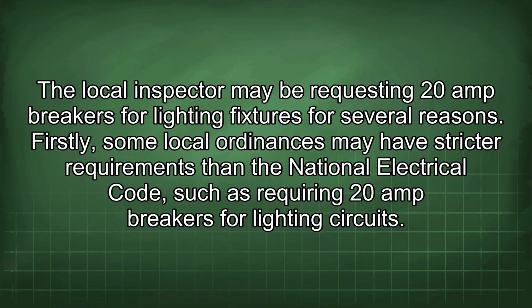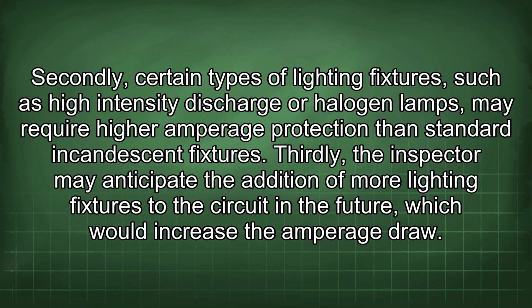The local inspector may be requesting 20-amp breakers for lighting fixtures for several reasons. Firstly, some local ordinances may have stricter requirements than the National Electrical Code, such as requiring 20-amp breakers for lighting circuits. Secondly, certain types of lighting fixtures, such as high-intensity discharge or halogen lamps, may require higher amperage protection than standard incandescent fixtures. Thirdly, the inspector may anticipate the addition of more lighting fixtures to the circuit in the future, which would increase the amperage draw.